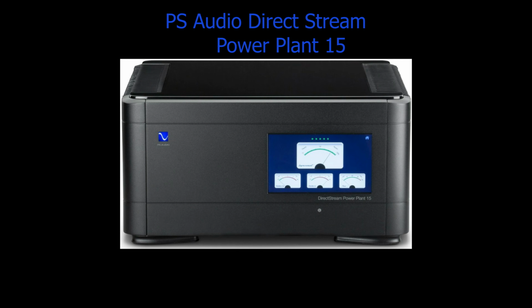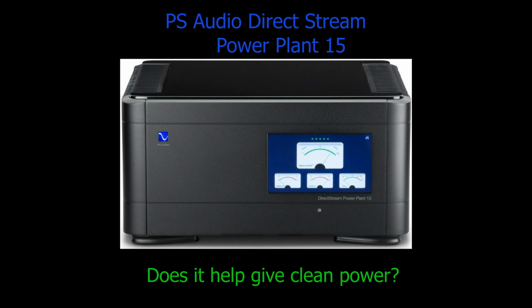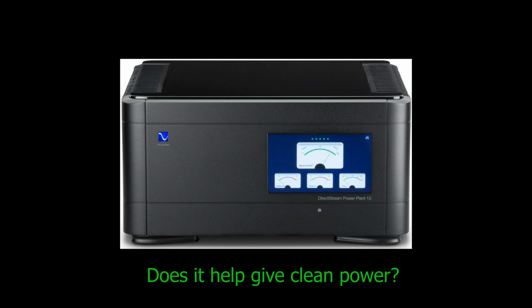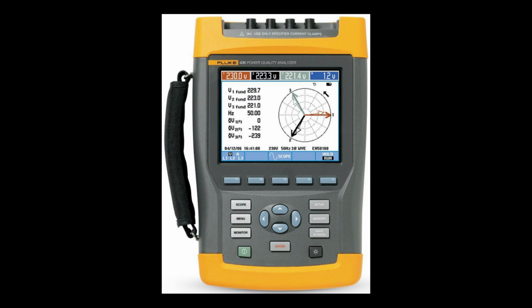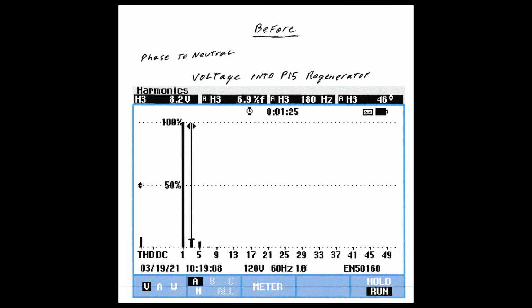Hello everyone, we're going to be taking a quick look at the PS Audio Power Plant 15 power regenerator. We're going to be using a Fluke 435 and measuring the harmonic distortion on the phase to neutral, both the input and the output of the Power Plant 15. The meter being used is a Fluke 435 power quality analyzer, and we'll be utilizing this meter to look at the harmonics that are present on the voltage input to the power regenerator and the voltage out of the power regenerator. Okay, let's jump right into it.